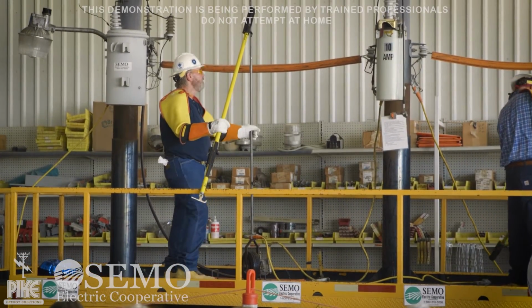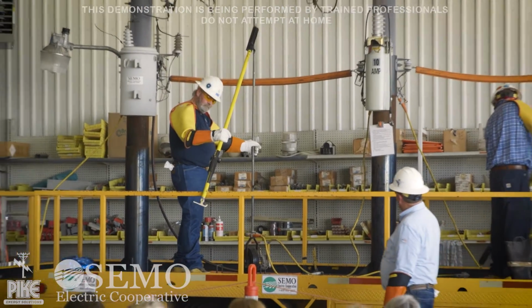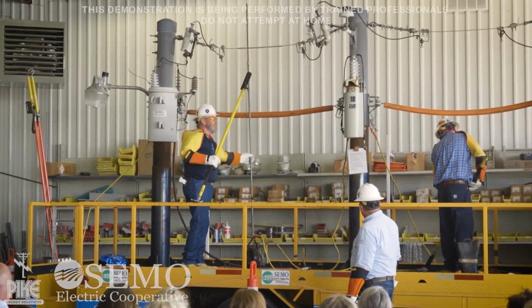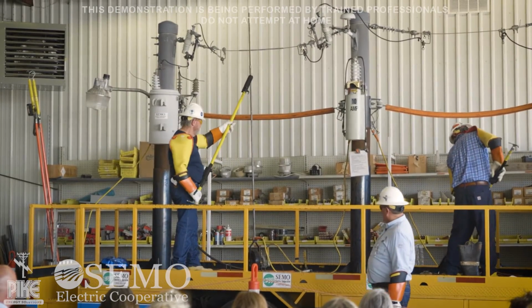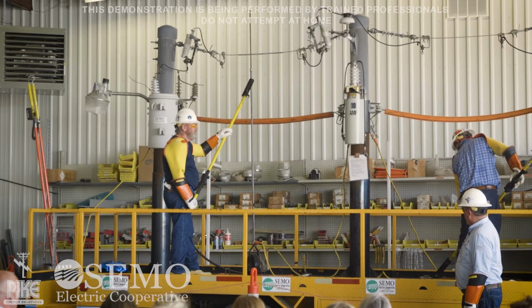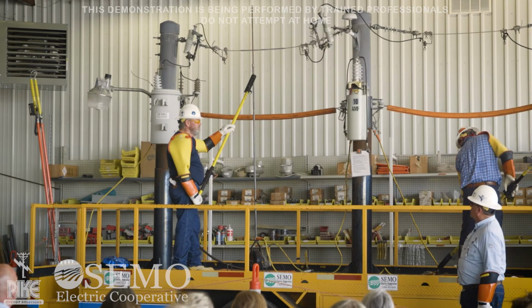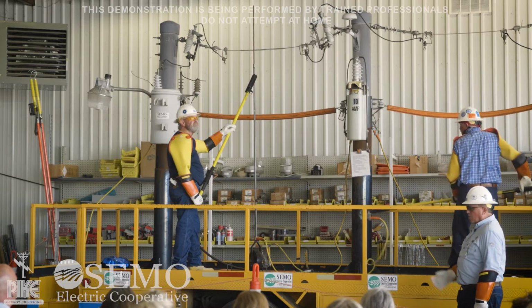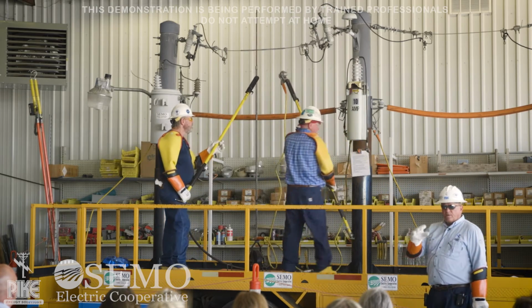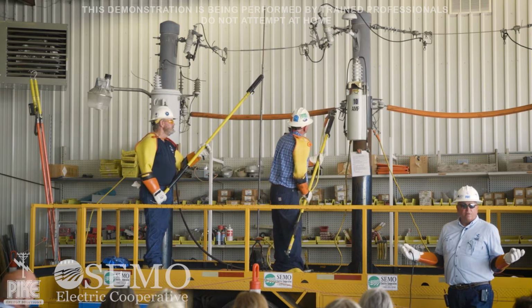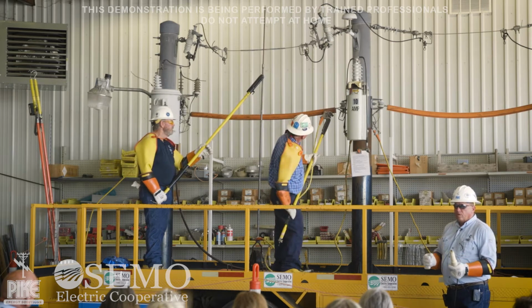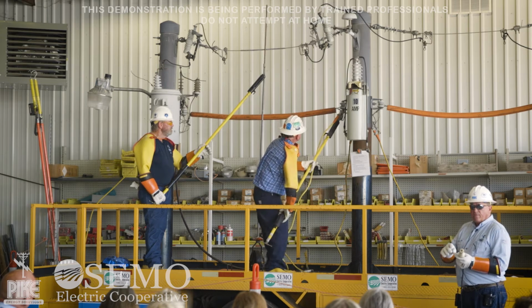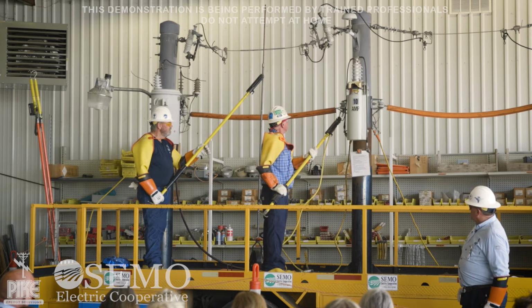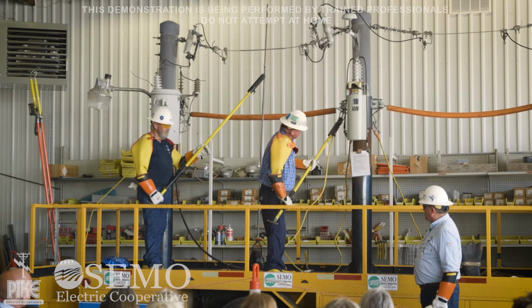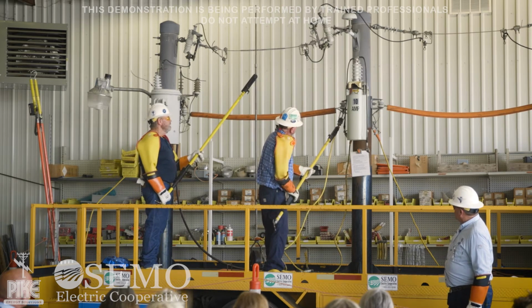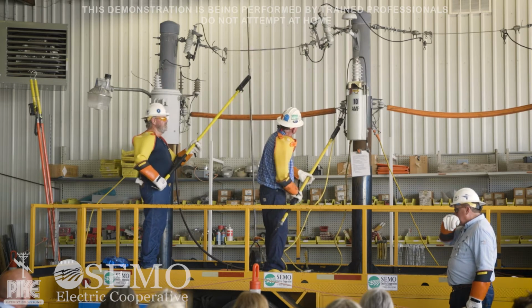Now we're going to take it and put it on the system neutral. That system neutral again is your bottom conductor right there. So all metal parts of line trucks, digger derricks, mobile cranes, pullers and tensioners shall be grounded. That's our rule here at Pike Electric. Y'all's rule may be a little different. Some companies barricade their equipment as well. We also do that for the most part, especially on our cranes. We have our cranes grounded. So you notice it's going to a system neutral there. That's your better ground. We're going to energize this again, do the same test again.